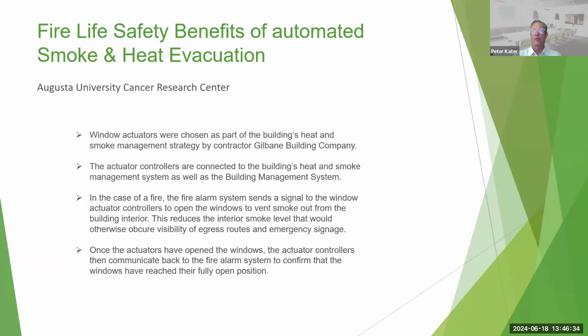This reduces the interior smoke level that would otherwise obscure visibility of signage, emergency signage, egress routes, etc. So it improves the survivability of the building in the event of a fire. Once the actuators have been told to open the windows and done so, the controllers will then, using the data feedback wiring that I mentioned earlier, communicate back to the fire alarm system, confirming that the windows have reached their fully open position. That way, the fire alarm system knows that the smoke and heat's being evacuated.